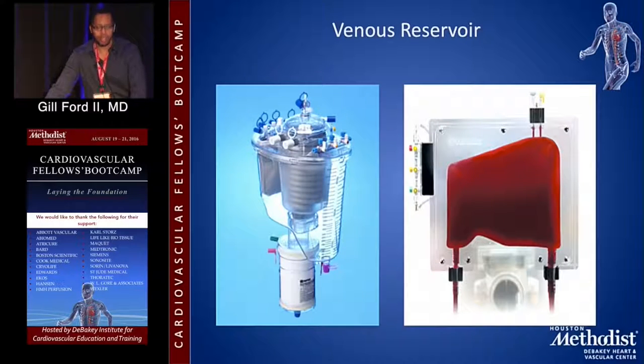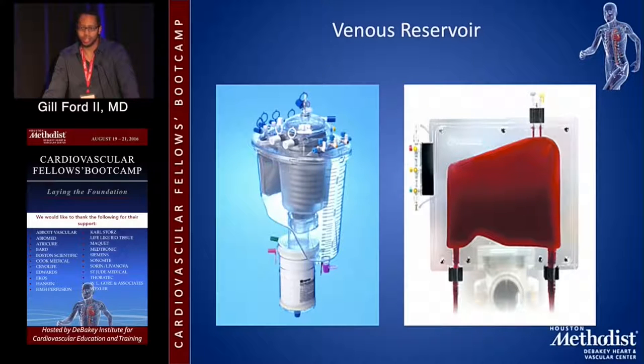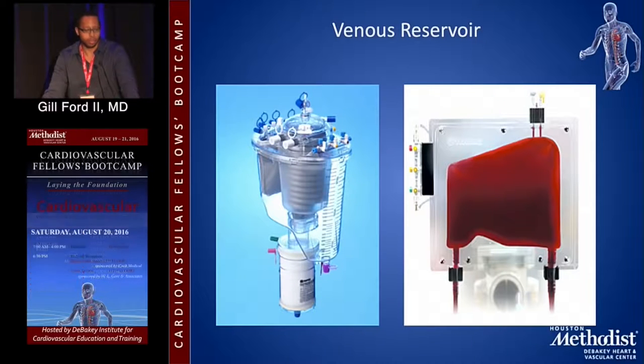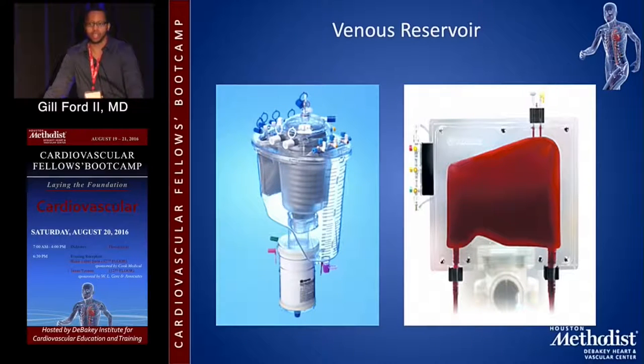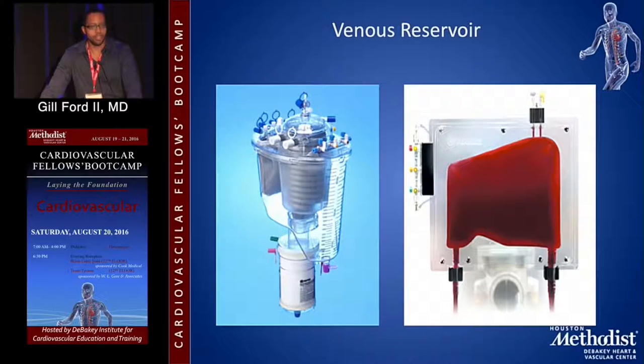After cannulating the patient, we connect using three-eighths inch or half-inch tubing. We drain the patient using either gravity or assisted venous drainage — either kinetic assist or vacuum — depending on the system used. Volume comes back into your venous reservoir, which essentially acts as the body of the patient, holding excess volume until we return it. You'll see both hard shell and soft shell reservoirs; the hard shell is most commonly used in most institutions.